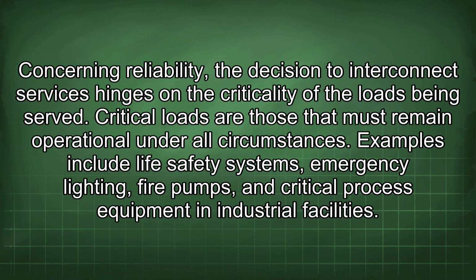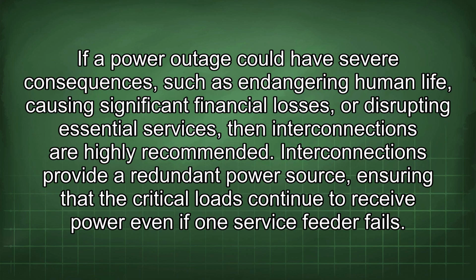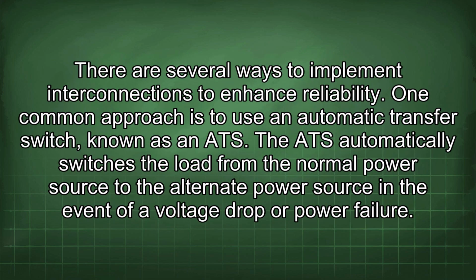Concerning reliability, the decision to interconnect services hinges on the criticality of the loads being served. Critical loads are those that must remain operational under all circumstances. Examples include life safety systems, emergency lighting, fire pumps, and critical process equipment in industrial facilities. If a power outage could have severe consequences, such as endangering human life, causing significant financial losses, or disrupting essential services, then interconnections are highly recommended. Interconnections provide a redundant power source, ensuring that the critical loads continue to receive power even if one service feeder fails.